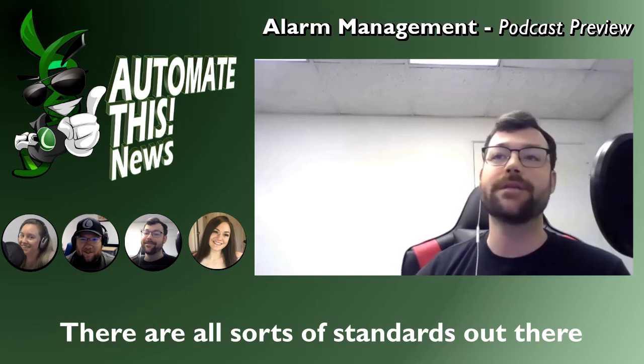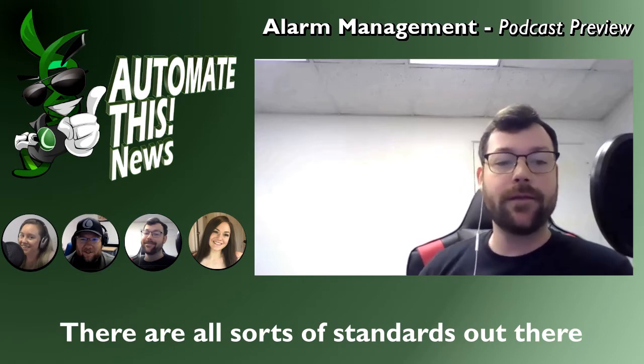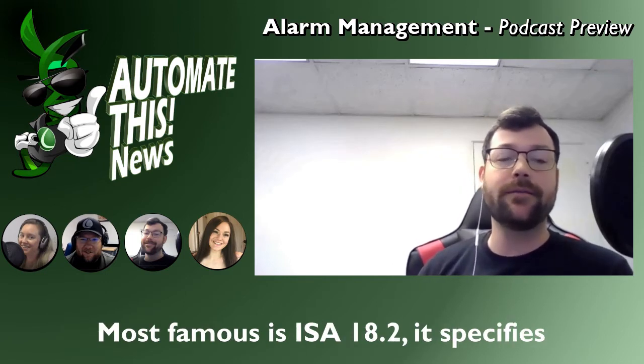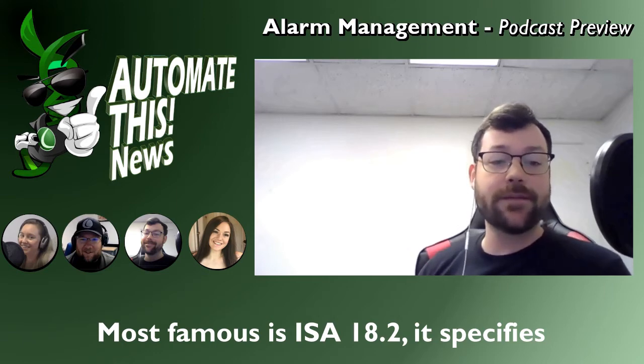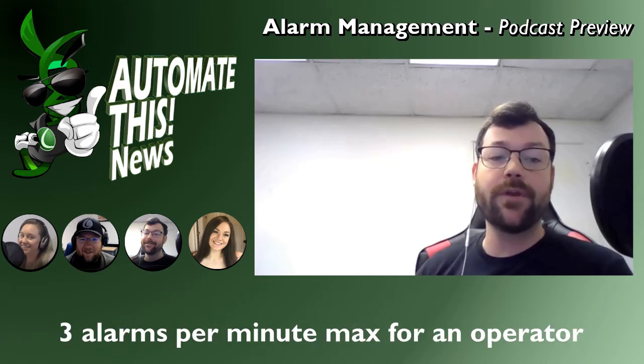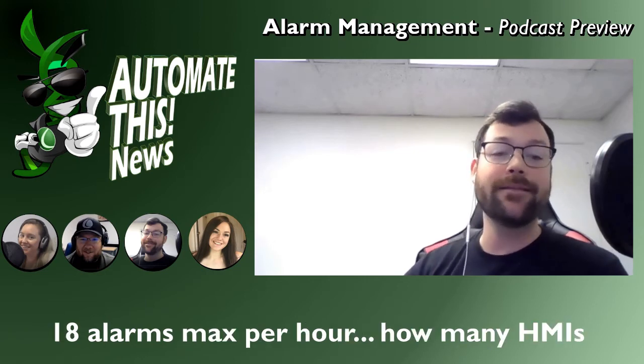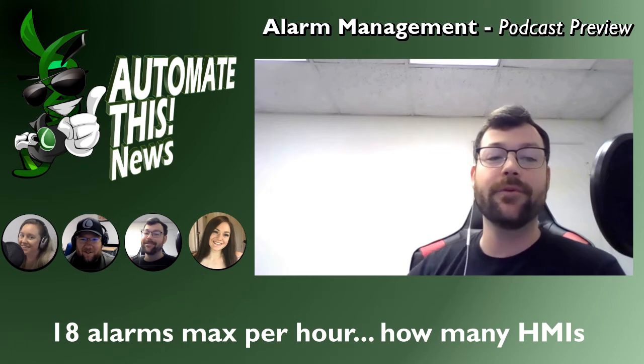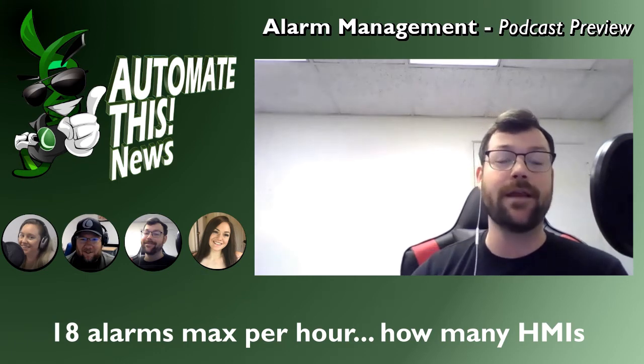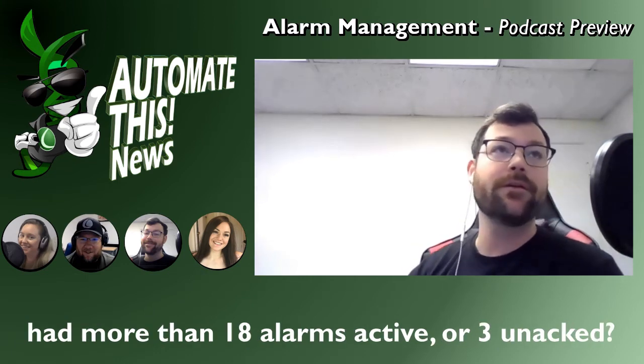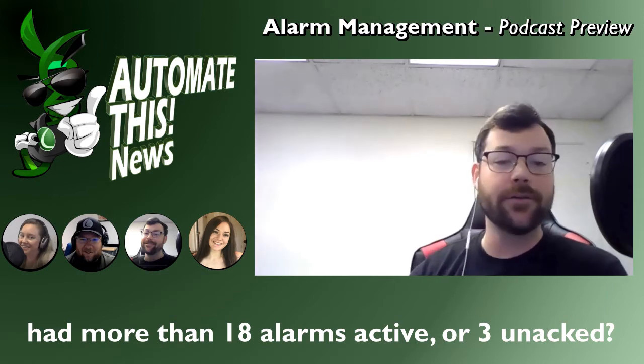And there's all sorts of standards out there that you can pore over. Like the most famous one, ISA 18.2, it specifies that per minute, 3 alarms is the max that an operator should ever see, and in an hour, 18 alarms is the max. Have you ever gone to an HMI that didn't currently have 18 alarms, either active or unacknowledged or whatever?